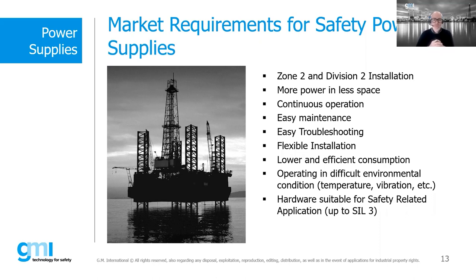Furthermore, the hot swapping function allows us to have easy maintenance. And at the same time, it allows us to have a device able to minimize downtime, because as we have already said, an interruption of normal operation can cause economic damage to the plant. Each power module mounted on a system with auto swap capability can be removed on its own without disrupting or affecting the application, which is another of the most frequent market requests.